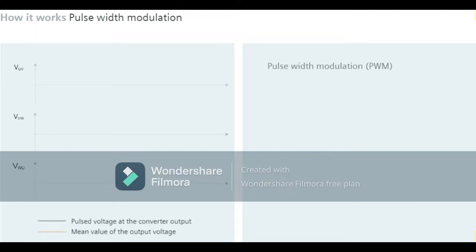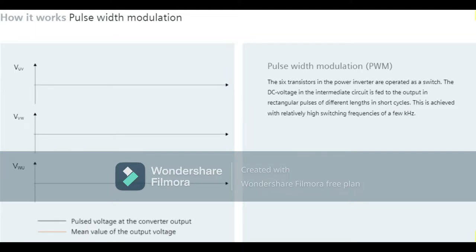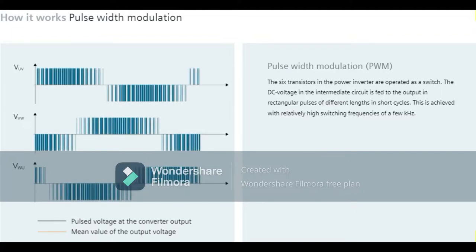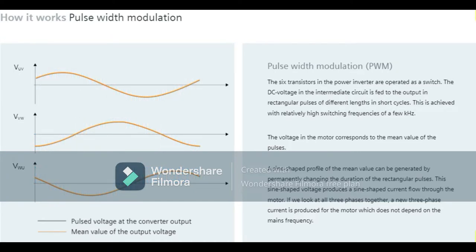Pulse width modulation, PWM for short, is a process which generates an analog signal from a digital signal. The transistors, as mentioned previously, are an integral part of the power inverter and are operated at a high switching frequency. The variable pulse-pause ratio is able to generate a sine-shaped profile for the mean current value. This produces a sine-shaped current profile, and if we look at all three phases together, a new three-phase current is produced for the motor which does not depend on the mains frequency.